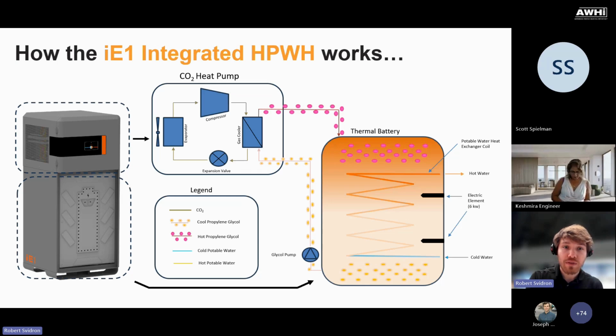Here's just a high level, quick schematic thrown together of how that thermal battery operates. It's hard to see it just from a cutaway picture. The idea is that you've got cooler propylene glycol supply at the bottom of the tank. That's what's going to feed your gas cooler here. We dump the hot propylene glycol supply at the top, so we've got some stratification. And then you've got a coil where your potable water supply moves through to heat up your water, with the two backup resistive elements here. As your building is using the water, it's being heated up, and then as necessary, the heat pump will turn on in order to recharge your thermal battery. If necessary, you've got backup electric resistive that will help maintain the state of charge in that battery at a high level.